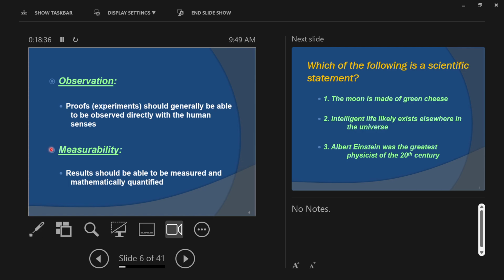We've got other measurements too, like our exposure deviation. That's a measurement. When we make an image, if you haven't taken images yet, we get our image on the screen, and we get a number associated with that image. It measures exposure. Are we high? Are we low? Are we right where we should have been, right with the expected value? That's a measurable thing. We get that with every image, and that's important because we can use that to adjust our technical factors. For example, we can increase or decrease on the next and following images. So that's the idea.